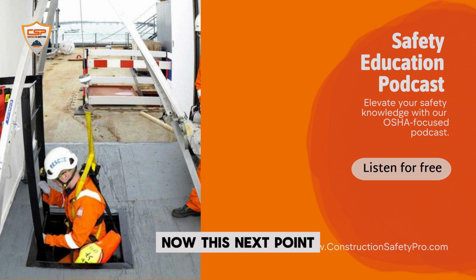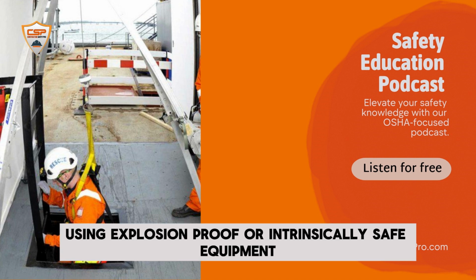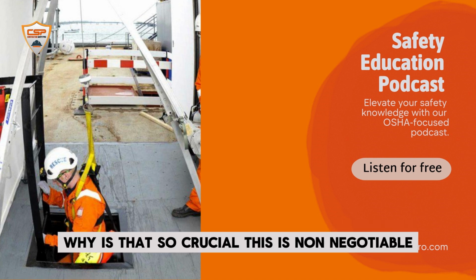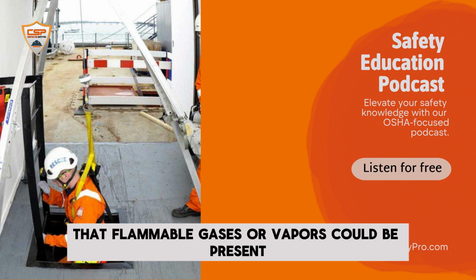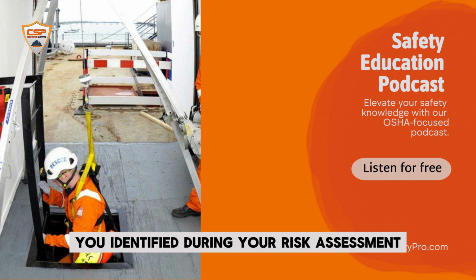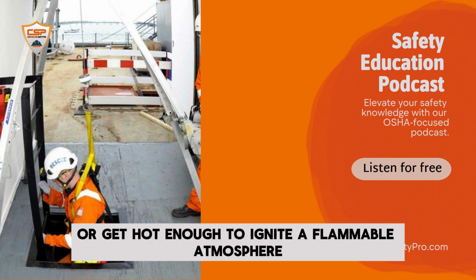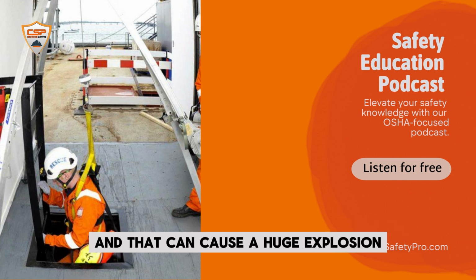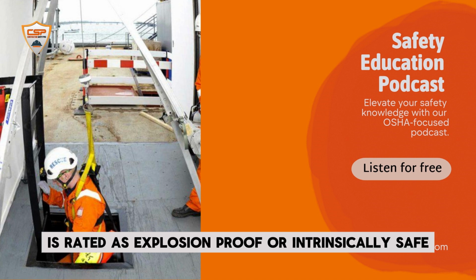Okay. Now, this next point was really stressed in the material: safety rating, specifically using explosion-proof or intrinsically safe equipment. Why is that so crucial? This is non-negotiable if there's any chance at all that flammable gases or vapors could be present, even if it's just a potential you identified during your risk assessment. Regular electrical equipment can spark or get hot enough to ignite a flammable atmosphere, and that can cause a huge explosion. That's why, if there's that risk, you have to make sure that your entire ventilation system, the fan, the motor, the ducts, even the electrical connections, is rated as explosion-proof or intrinsically safe.